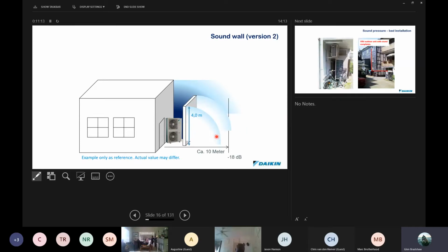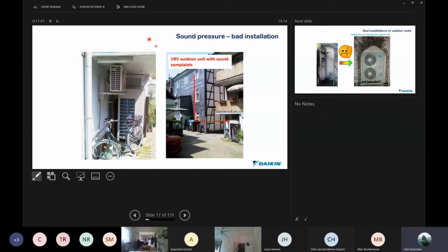If we increase the height of that wall over here, basically here we can eliminate most of the sound. Remember again with the height of the wall that this mustn't cause recirculation of the condenser air. So for a vertical discharge machine this might work better than it would for a horizontal discharge machine.